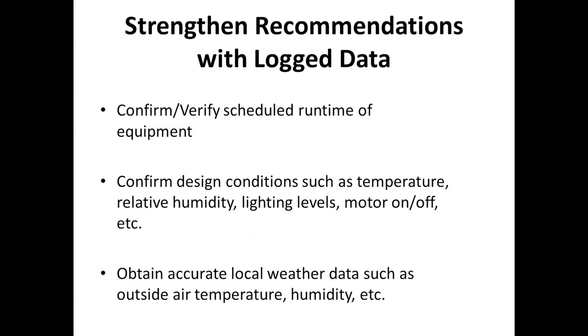And it's important, really, data logging can be used to verify what we thought were existing conditions and how we broke down energy usage. But we can also use it to strengthen recommendations for energy conservation measures. Most commonly, we can verify scheduled runtime of equipment, temperature, set points, relative humidity, lighting levels, outside air temperature, humidity.